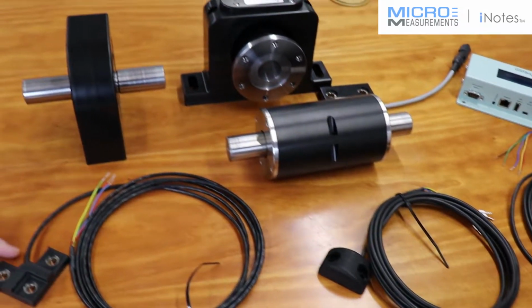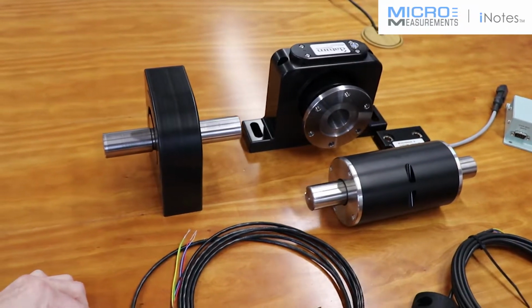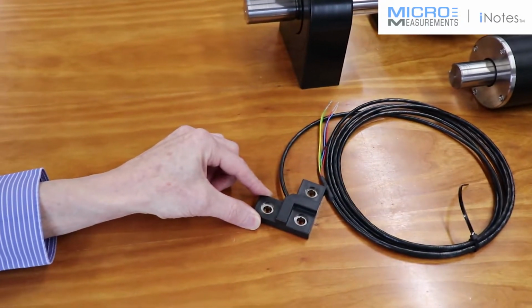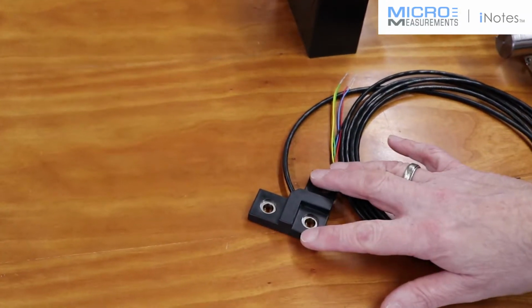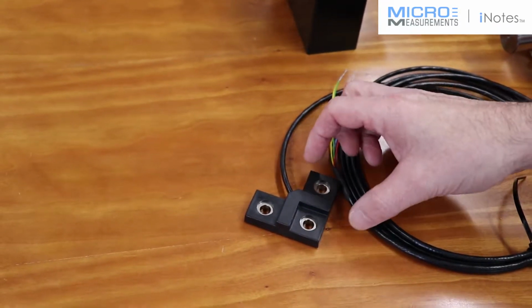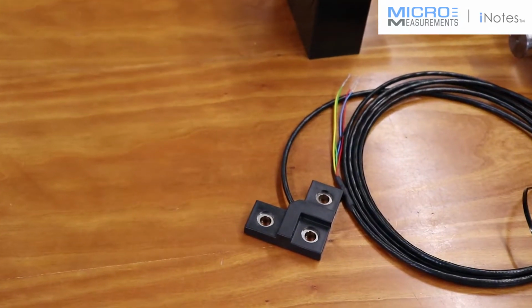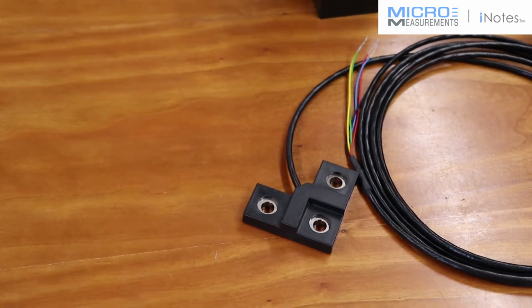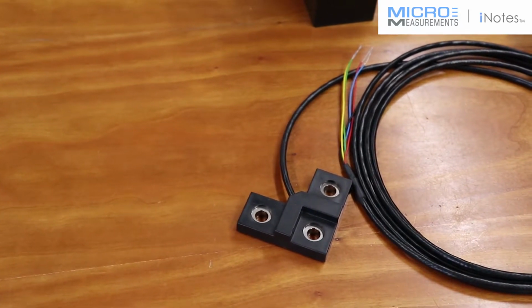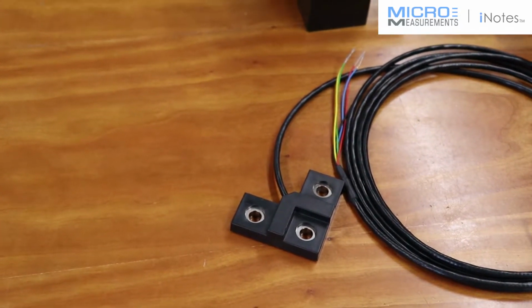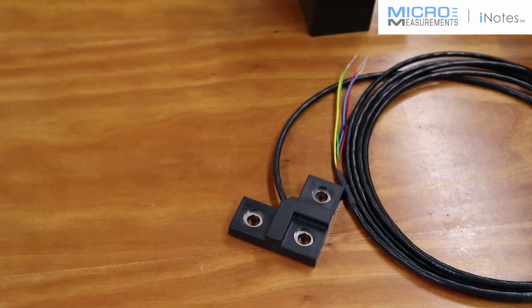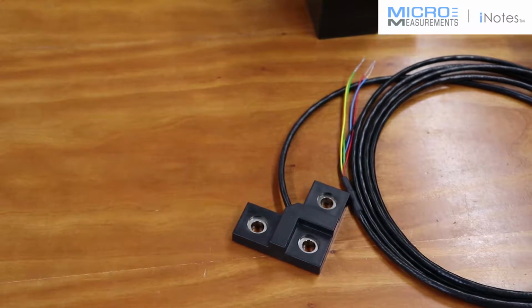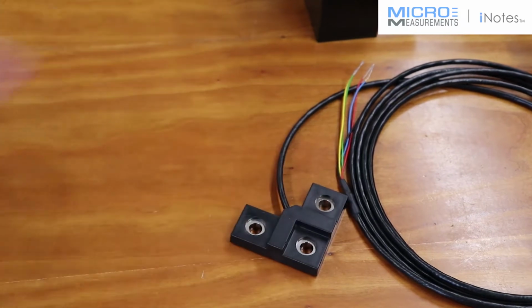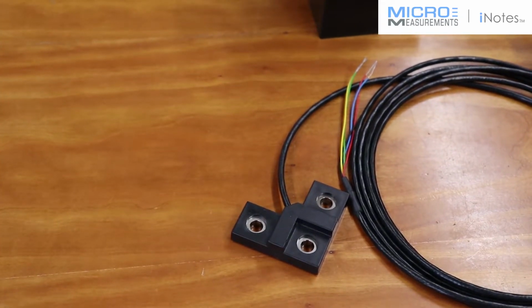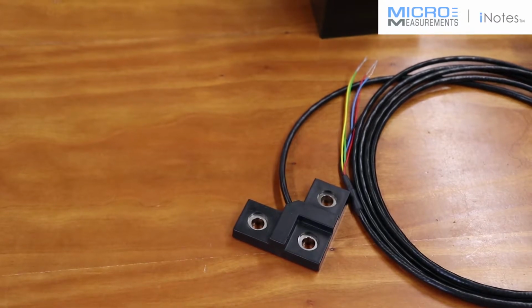This particular transducer is designed to overcome thermal transients that cause false alarms in an application. Using a simple principle, we can overcome things like rapid changes in temperature, again on things like vehicle gearboxes and axles. When a rapid change in temperature occurs, this sensor stops the alarm going off because it cancels it out, you have one active part of the sensor and one dummy part, which eliminates that thermal transient. Again, very simple to install.